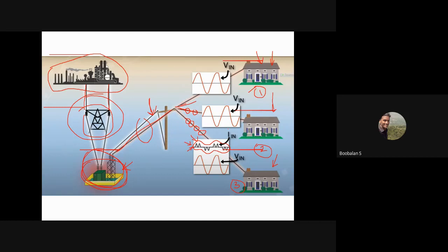Due to my inductive load, such as induction motors, a phase angle is introduced between my voltage and current waveform, and for that we use a capacitor. With the help of the capacitor, providing what is called kVAR, you can compensate and correct your power factor. So those things will be useful over there. The same way in harmonics, how could we reduce it?